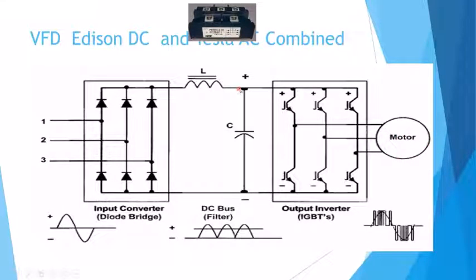But the bottom line is the VFD came on, and they had these bridge diodes on the front end. This is what they call a link choke inside the drive. Some people will put coils out here, and that'll be what they call a line reactor, and that will dampen it. I'll get into the reason why they did that. Then it has capacitors in here.